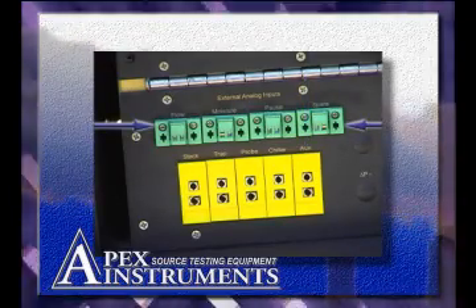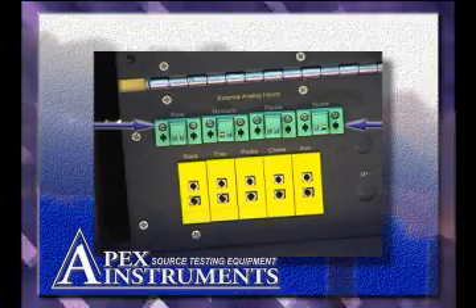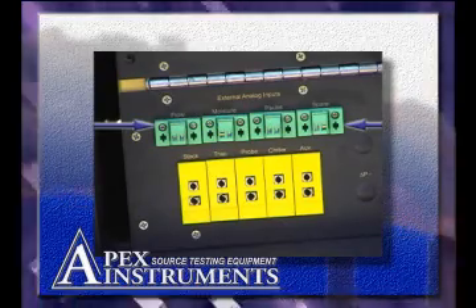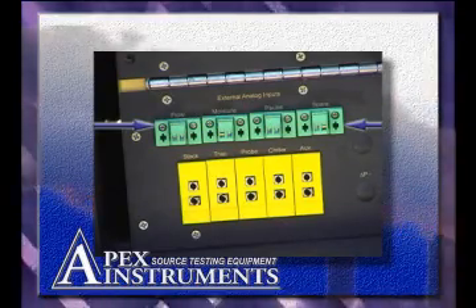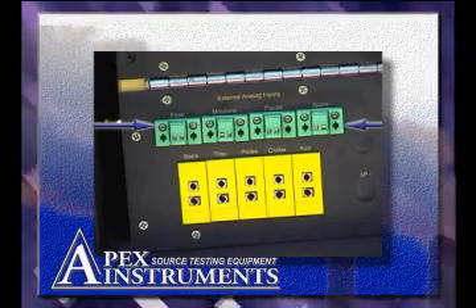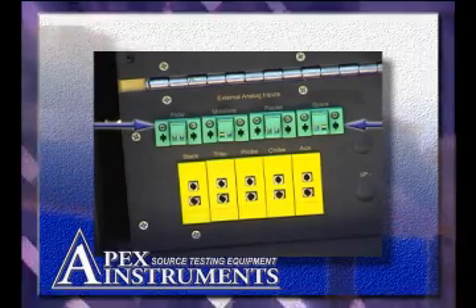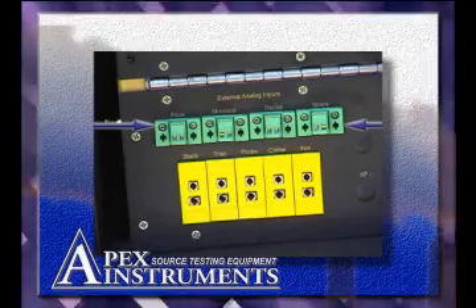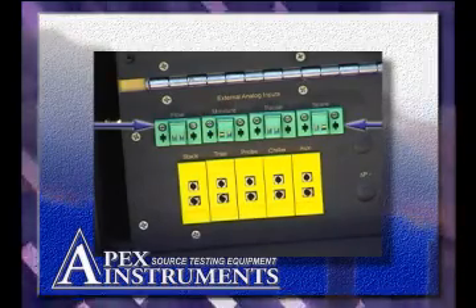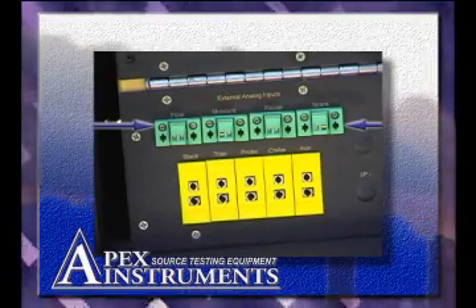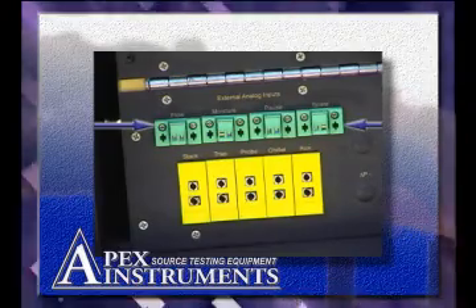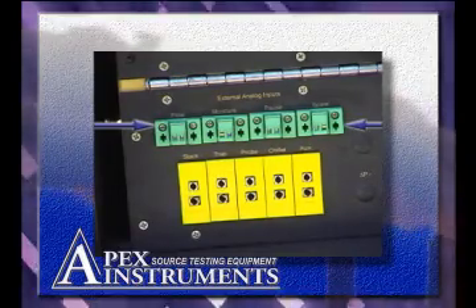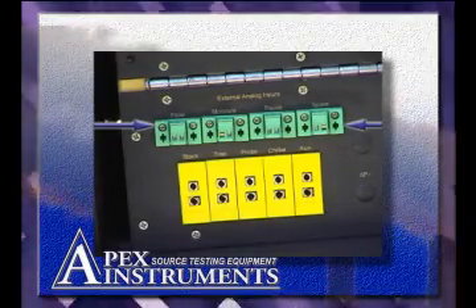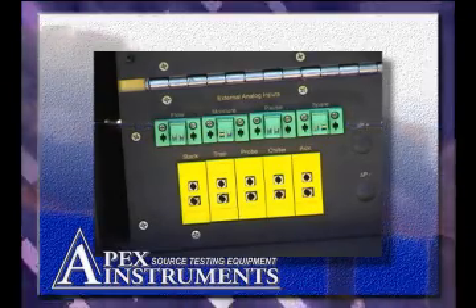Above the thermocouple connections, there are 4 connectors that are for remote signal inputs. Analog input for stack flow and moisture, as well as remote pause input, which can be used to pause or stop a test. There is a spare connector that can be used as a contact output for alarm purposes. Signals from this connection can trigger visual or audible alarms.